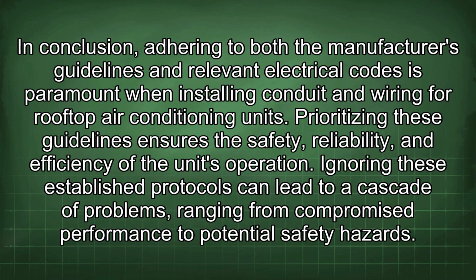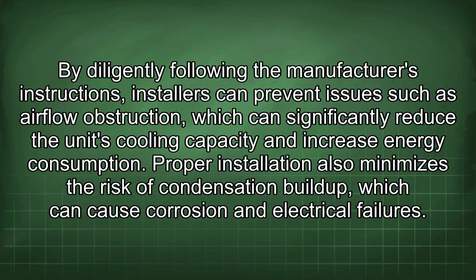In conclusion, adhering to both the manufacturer's guidelines and relevant electrical codes is paramount when installing conduit and wiring for rooftop air conditioning units. Prioritizing these guidelines ensures the safety, reliability, and efficiency of the unit's operation. Ignoring these established protocols can lead to a cascade of problems ranging from compromised performance to potential safety hazards. By diligently following the manufacturer's instructions, installers can prevent issues such as airflow obstruction, which can significantly reduce the unit's cooling capacity and increase energy consumption.